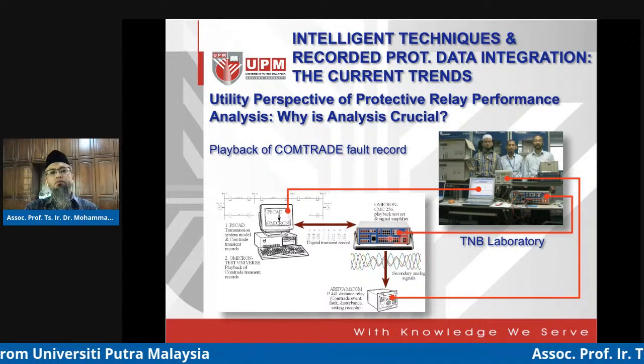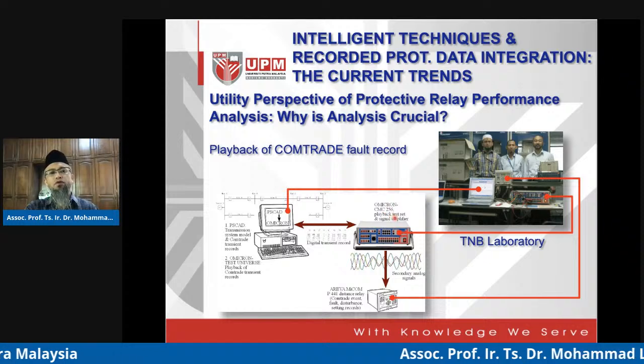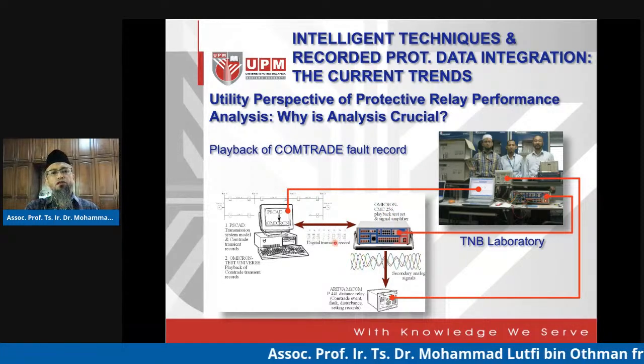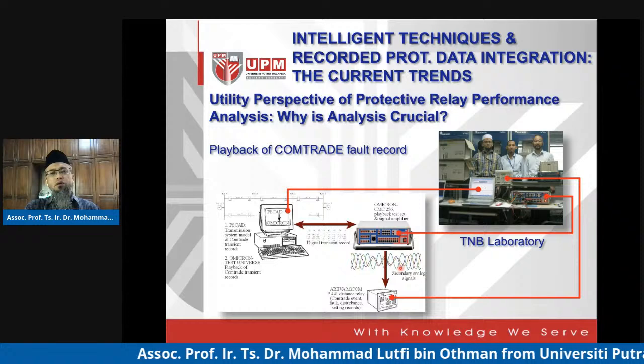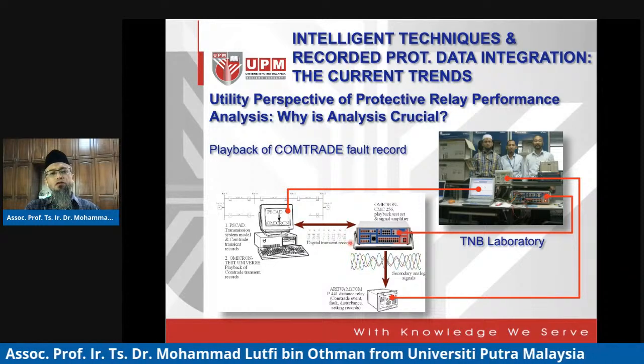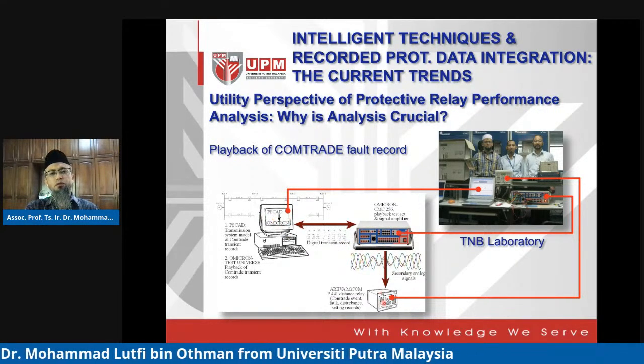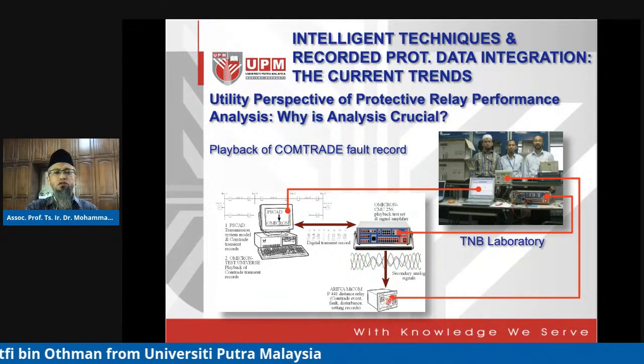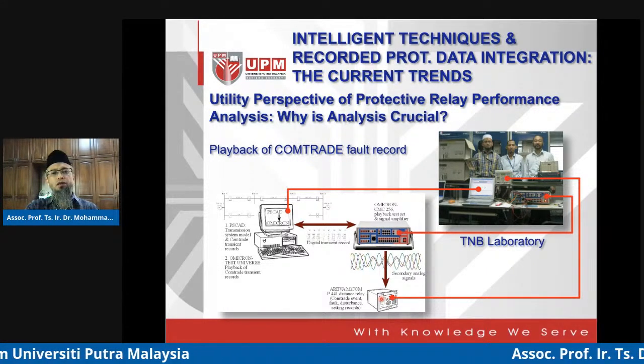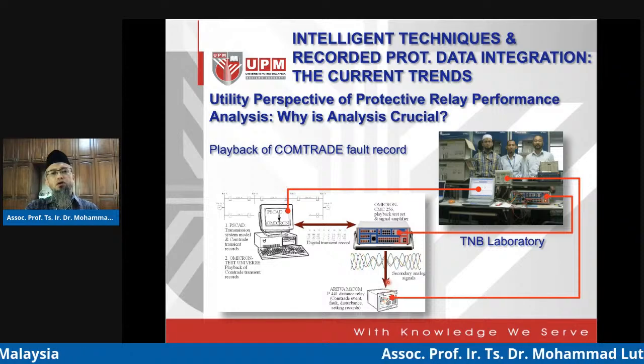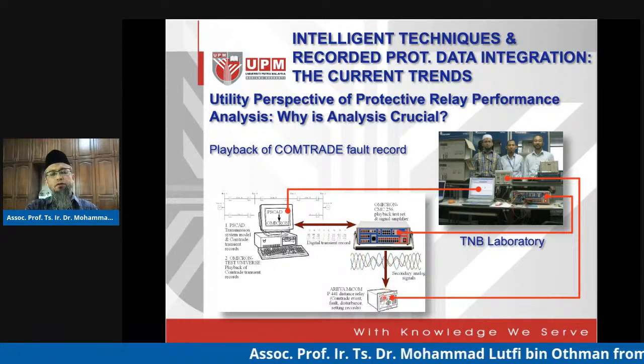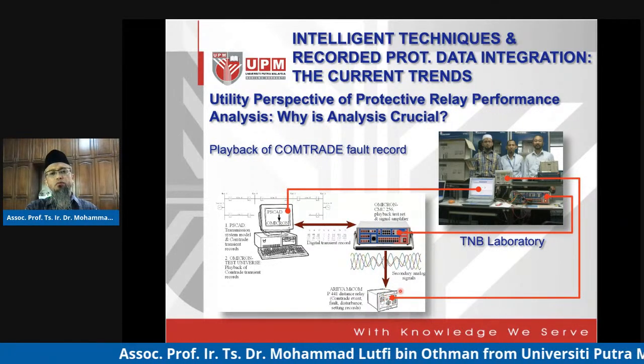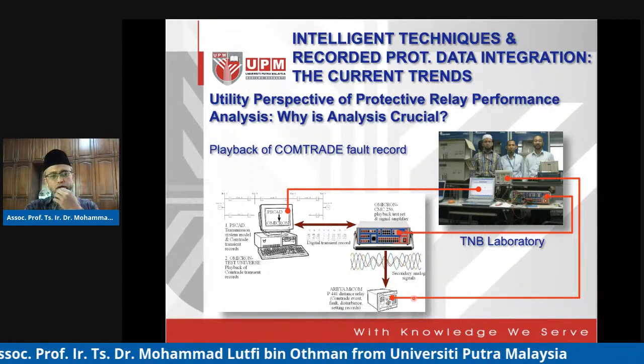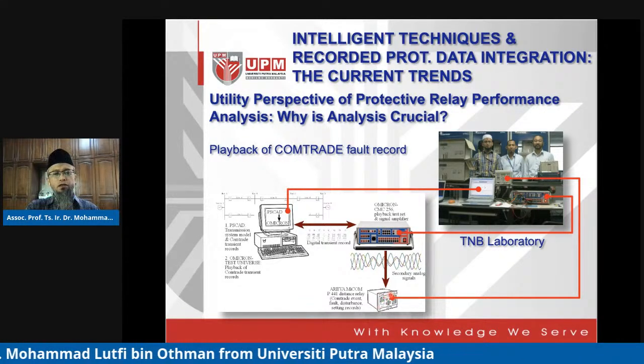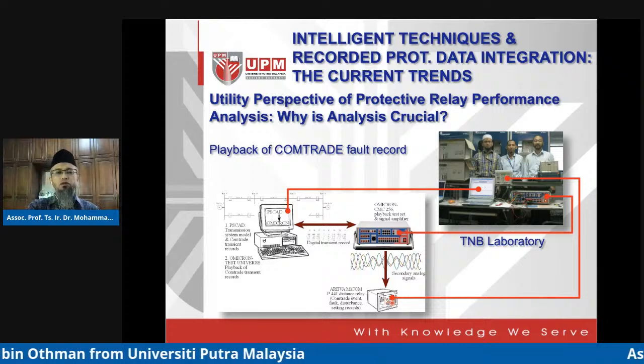This playback test set, Omicron CMC 256, is able to inject the secondary value of the voltage or currents provided by the model power system into the actual relay, the Areva MiCOM P441 distance relay. Instead of the actual relay, you can also substitute it with our own model relay. What I'm going to talk about is simply the relay we are going to deal with, which is actually a model relay, as I'll present later.